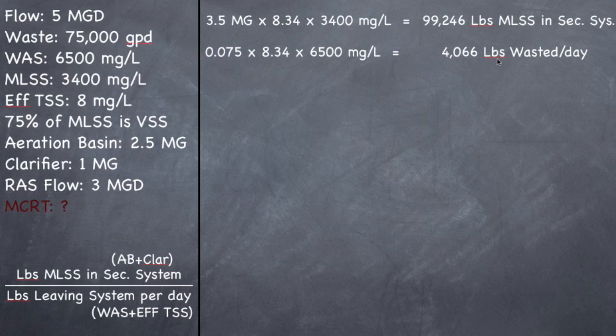So we figured out how many pounds wasted per day, your WAS. Now we need to find out the effluent TSS. So we'll multiply 5 MGD, which is our flow, times 8.34 pounds per gallon times 8 milligrams per liter, which is my effluent TSS concentration. You should get 334 pounds of TSS discharged per day.